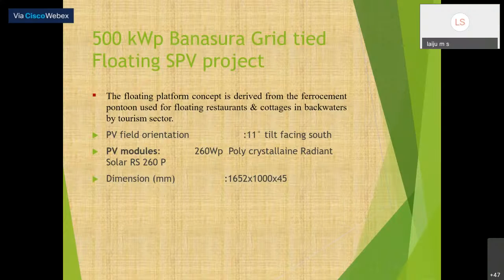So the number of modules we have selected is 18 by 6, 19 by 6, and finally we arrive at a design of 23 by 5, that is 115 into 0.26, which is around 29.9, so 30 kW. How much capacity will be generated from each float? That is around 30 kW. Each inverter, the company says, we can load more. So the assured capacity will be 30 kW from each float, and 17 floats are coming.